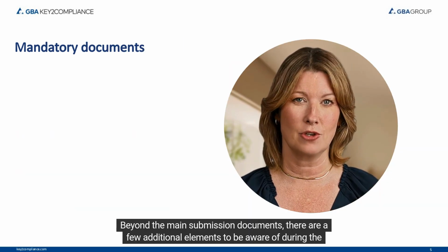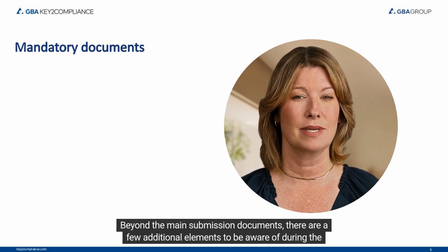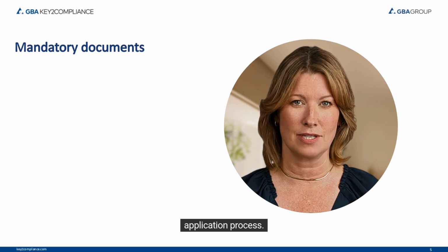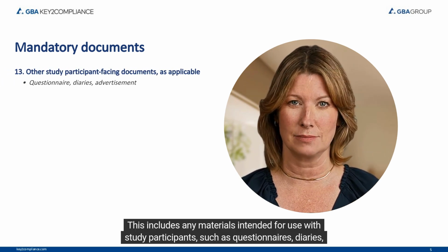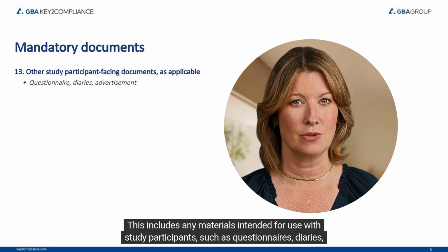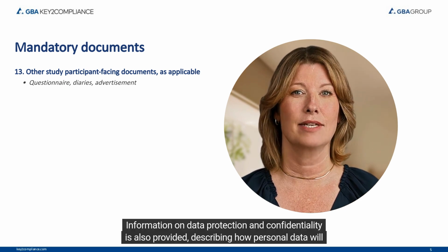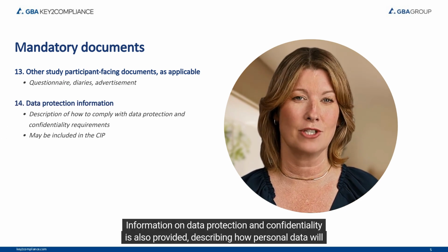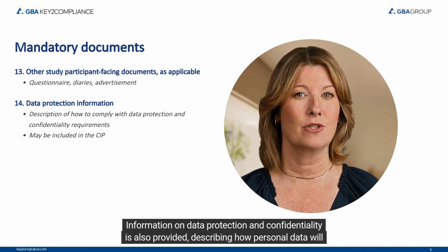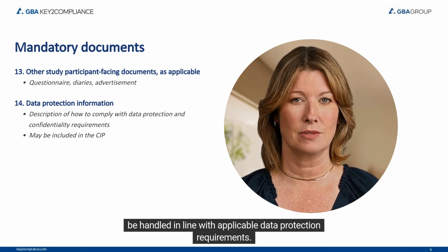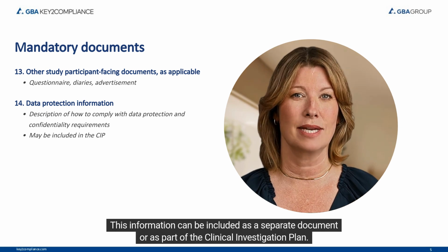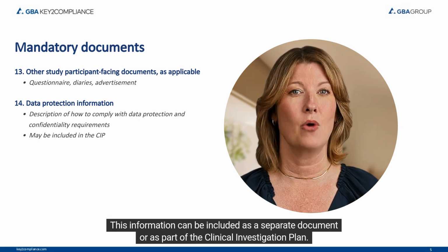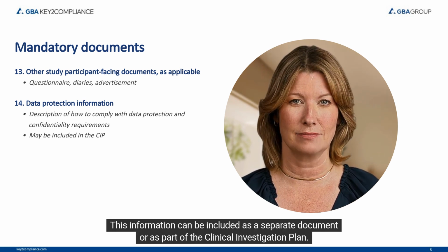Beyond the main submission documents, there are a few additional elements to be aware of during the application process. This includes any materials intended for use with study participants, such as questionnaires, diaries, or advertisement materials. Information on data protection and confidentiality is also provided, describing how personal data will be handled in line with applicable data protection requirements. This information can be included as a separate document or as part of the clinical investigation plan.